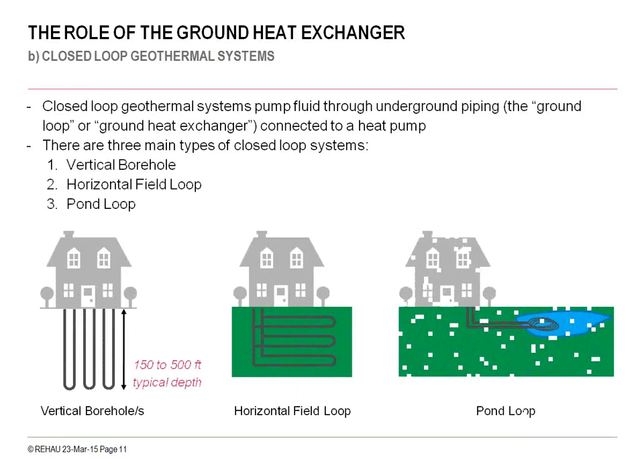Closed loop geothermal systems. Three main types: vertical boreholes, where we're going down hundreds of feet with say a 5 or 6 inch diameter borehole. Horizontal loop fields, where we'd be going down maybe 6 feet, 8 feet from the surface, and then a pond loop where we are utilizing a body of water in lieu of the earth for acting as the condenser for the heat exchange.